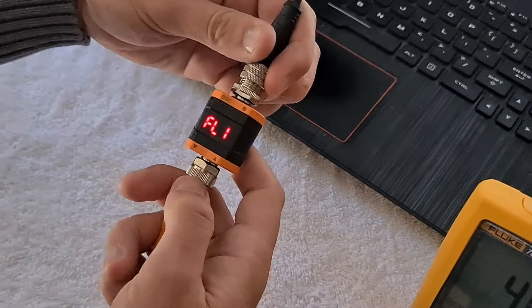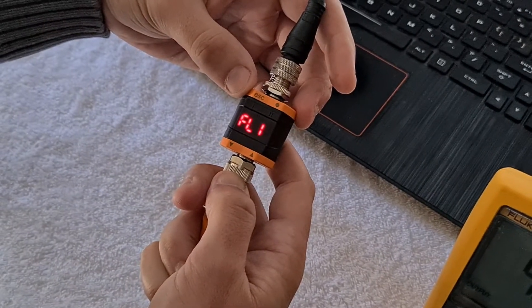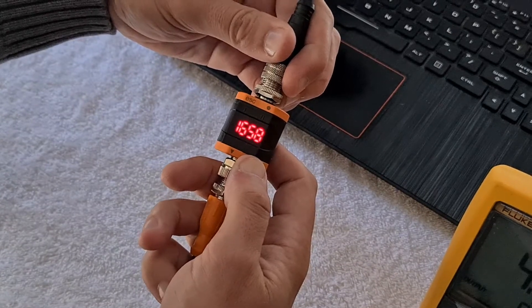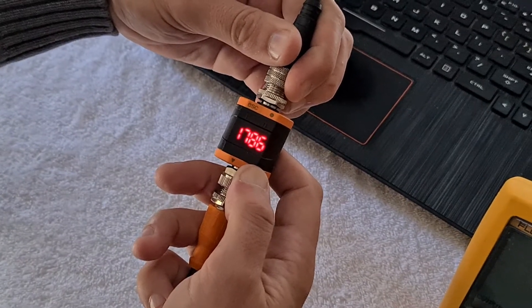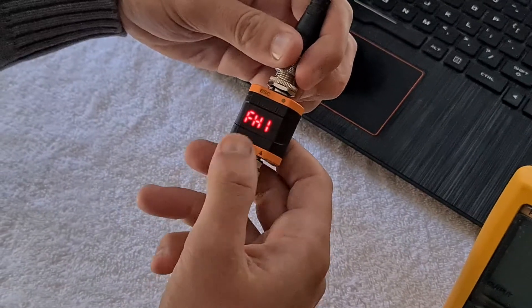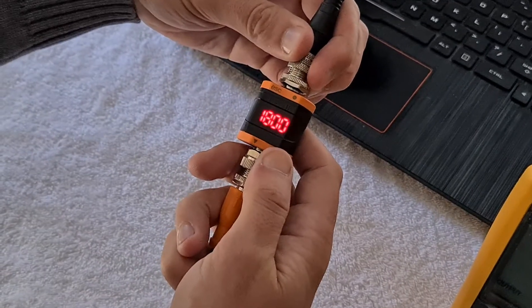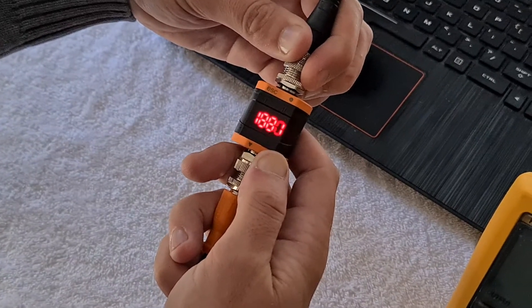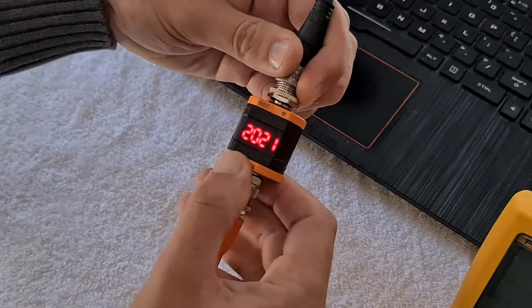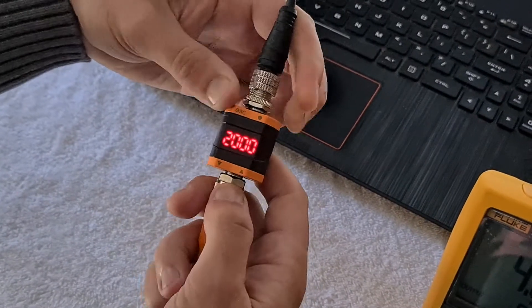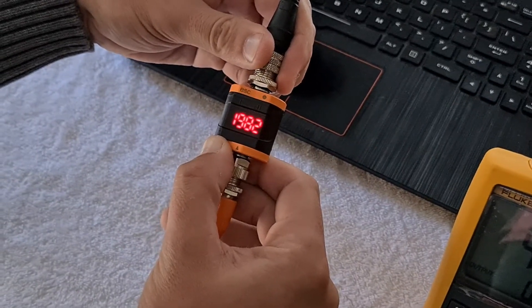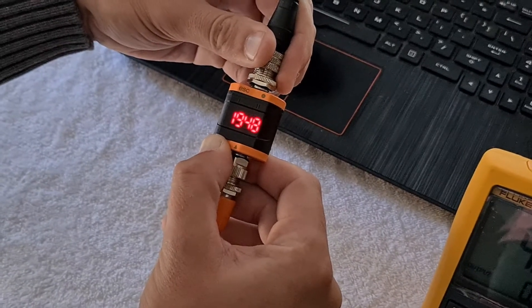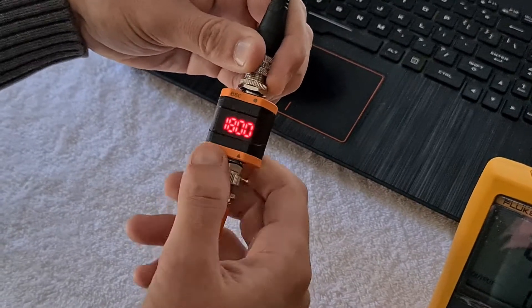Down from there, FL1. That's going to be 1800. It's stuck. It's locked because the other one is too low. So I'll just go set that. Set the high point first before the low point. That's the 2000 PSI at the end of your alarm window. So 2000. Save that. And now set the FL. You'll be able to adjust that to 1800. Save that.